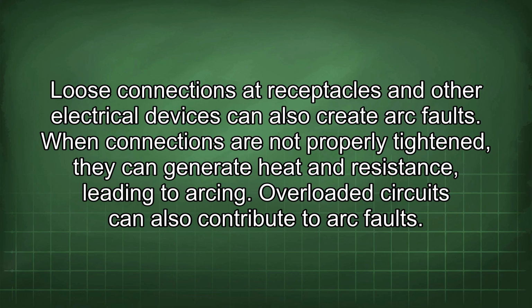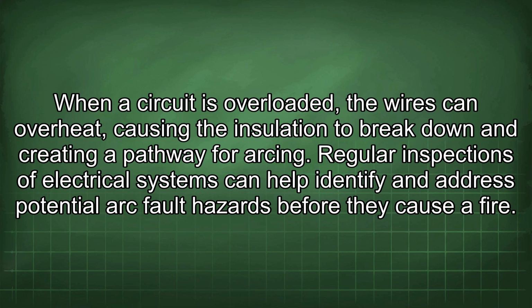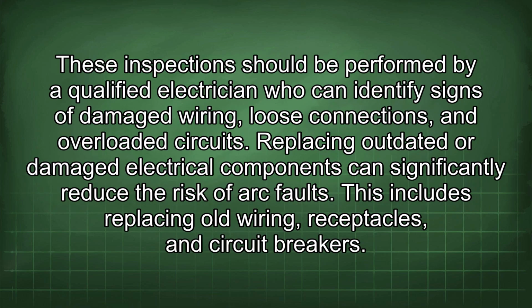Overloaded circuits can also contribute to arc faults. When a circuit is overloaded, the wires can overheat, causing the insulation to break down and creating a pathway for arcing. Regular inspections of electrical systems can help identify and address potential arc fault hazards before they cause a fire. These inspections should be performed by a qualified electrician who can identify signs of damaged wiring, loose connections, and overloaded circuits. Replacing outdated or damaged electrical components can significantly reduce the risk of arc faults.